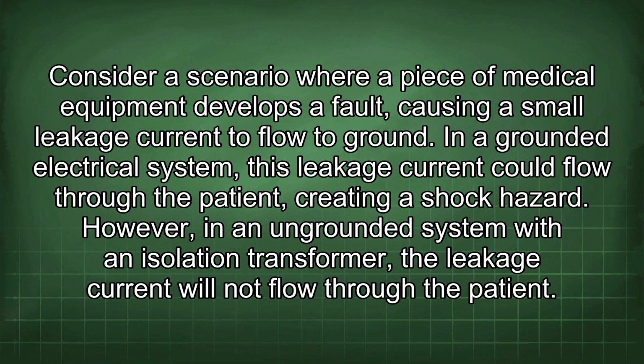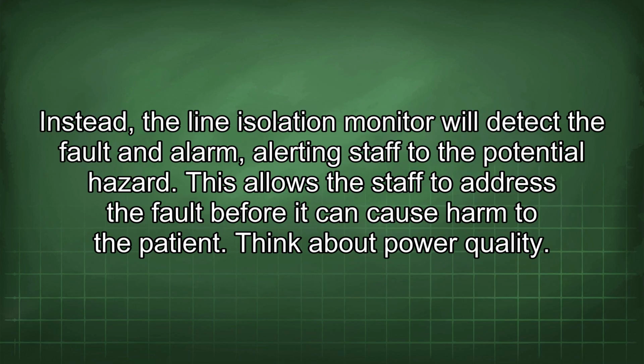However, in an ungrounded system with an isolation transformer, the leakage current will not flow through the patient. Instead, the line isolation monitor will detect the fault and alarm, alerting staff to the potential hazard. This allows the staff to address the fault before it can cause harm to the patient.